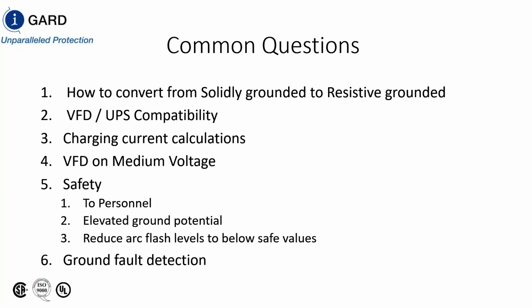So I want to thank everybody for listening to my simplistic view of what's going on. I'm more of a practical guy out here in the field. Certainly, if you have any questions about HRGs, Sergio is the guy to run them through. But if you want to contact me through him, that's fine too. On real world applications, there's questions I've gotten like, how do you mount the CTs? Well, your CTs need to be mounted on your secondary as close to the transformer as possible. And then, what kind of structural arrangements do you need to have? These are things that you need to consider when you're doing protections on your substations, not just HRGs.